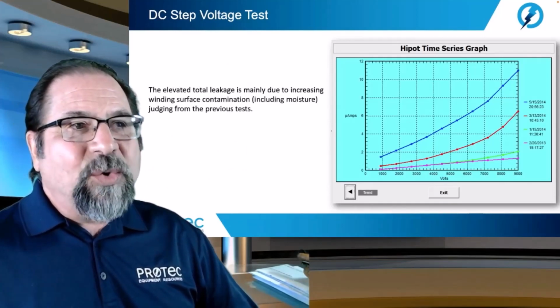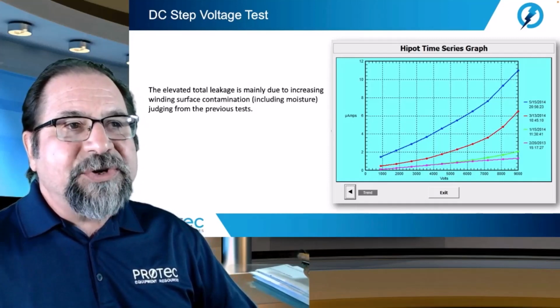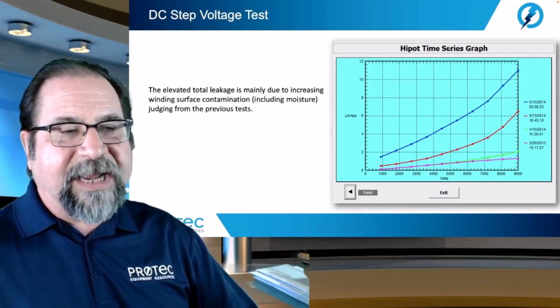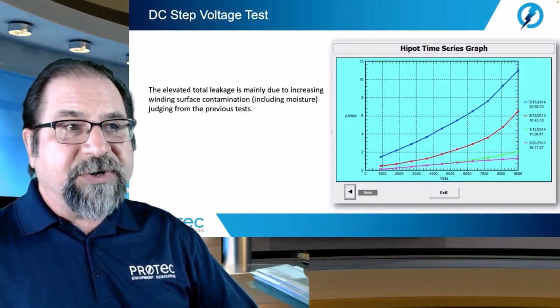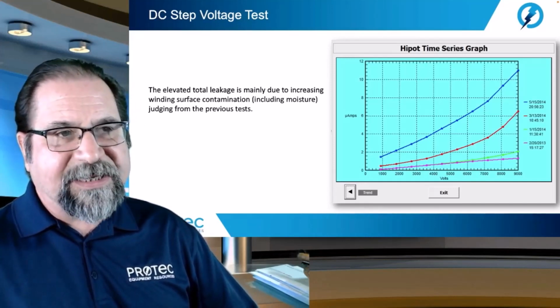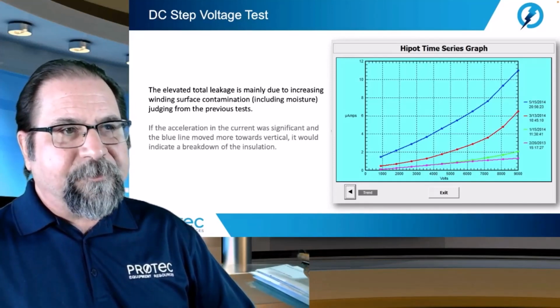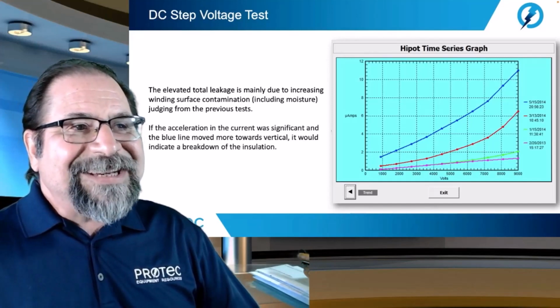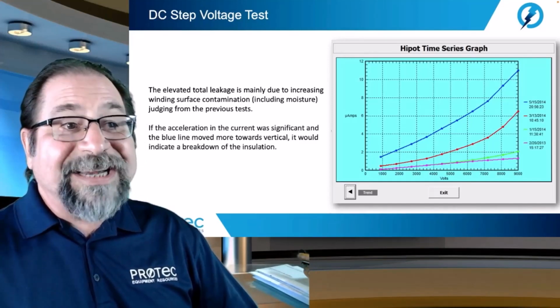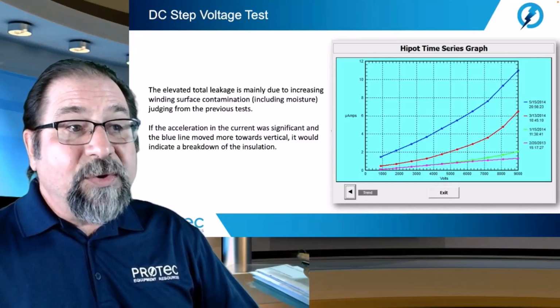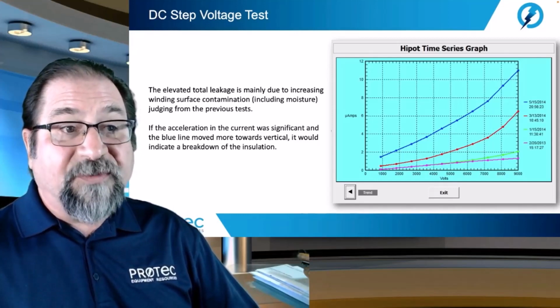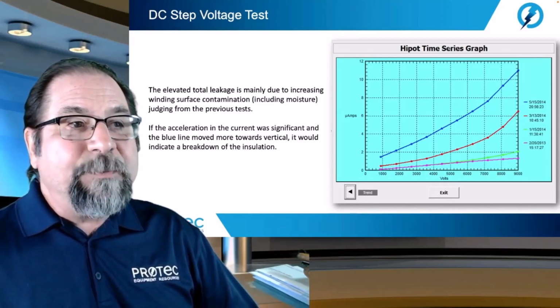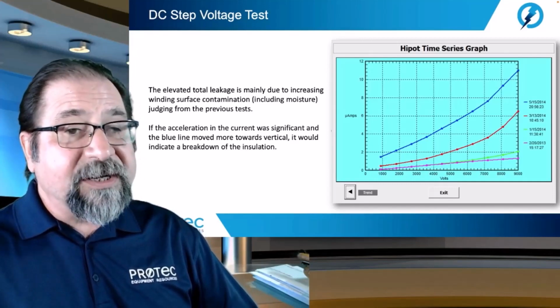The elevated total current is mainly due to increasing winding surface contamination, including moisture, judging from the previous tests. If the acceleration in the current was significant and the blue line moved more towards vertical, it would indicate a breakdown of the insulation.